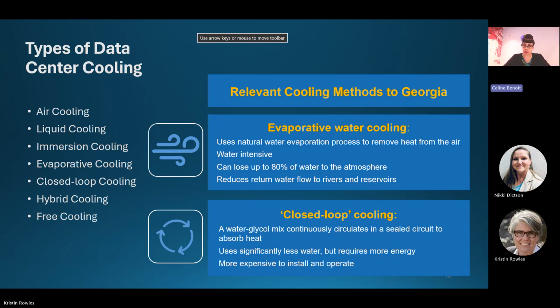In comparison to evaporative cooling, which is a once-through cycle, closed loop cooling uses a water glycol mix that circulates within the system at several concentrations. So it uses significantly less water, but in turn requires more energy. There are always trade-offs with these different approaches. It's also more expensive for the developer to install when constructing the site, and it can require a larger physical footprint within the data center itself - potentially lost space that could have gone to servers. So it's important, when these proposals come in, to identify the type of cooling being proposed for the site.